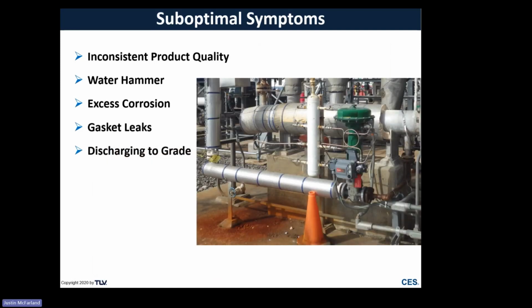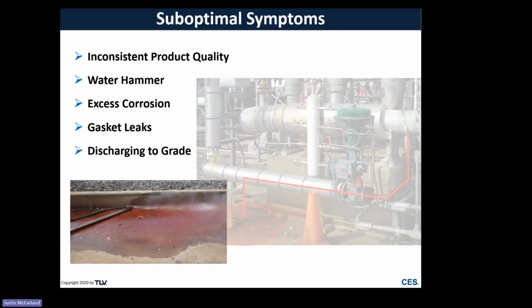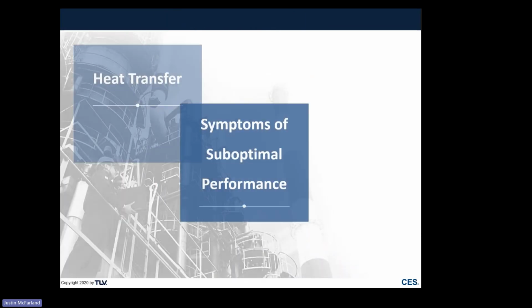And discharging to grade seems like, well, that's not how the system was designed. Why is this happening? Typically, an operator's primary job is to make sure that the process heater is operating and the process is being heated to what the spec is. So if something starts to go awry, usually an operator is going to say, okay, the easiest thing for me to do is open up a bypass valve or open up a drain and drain all the condensate to the sewer. A lot of times that fixes the problem, but that's not how the system was designed. And so it's wasteful, with water loss and energy loss, but that's another red flag that something's going wrong here that shouldn't be happening.